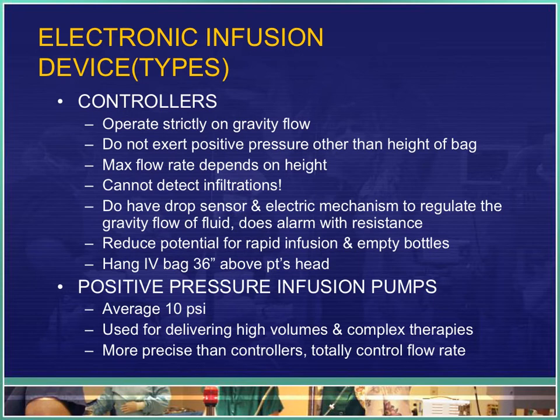Controllers operate strictly on gravity flow. They do not exert positive pressure other than the height of the bag. Max flow rate depends on height. You cannot detect infiltrations. They do have drop sensors and electric mechanisms to regulate the gravity flow of fluid and will alarm with resistance. They reduce potential for rapid infusion and empty bottles. Hang the IV bag 36 inches above the patient's head.